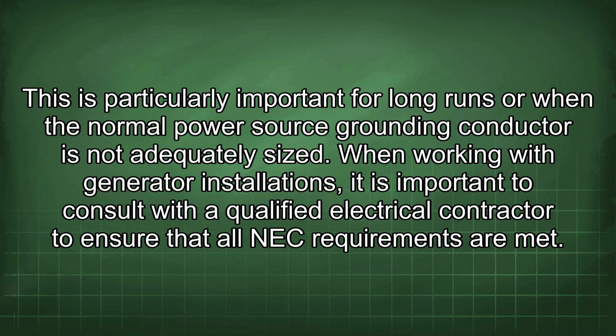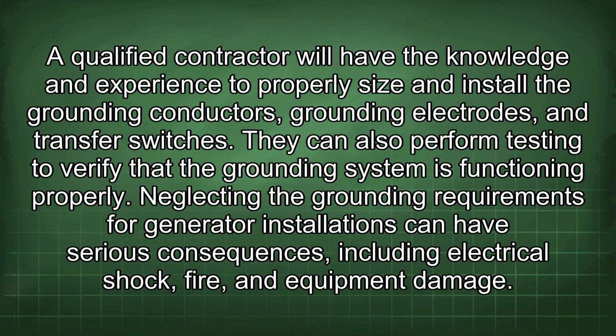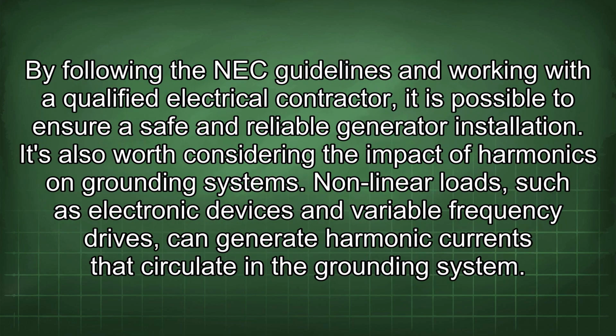When working with generator installations, it is important to consult with a qualified electrical contractor to ensure that all NEC requirements are met. A qualified contractor will have the knowledge and experience to properly size and install the grounding conductors, grounding electrodes, and transfer switches. They can also perform testing to verify that the grounding system is functioning properly. Neglecting the grounding requirements for generator installations can have serious consequences, including electrical shock, fire, and equipment damage.